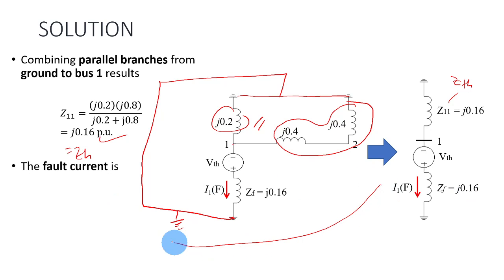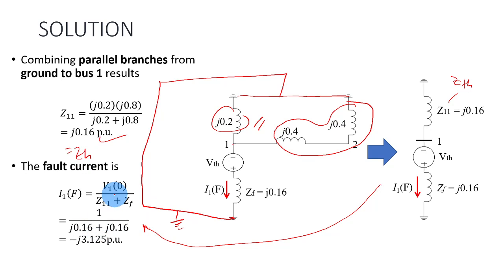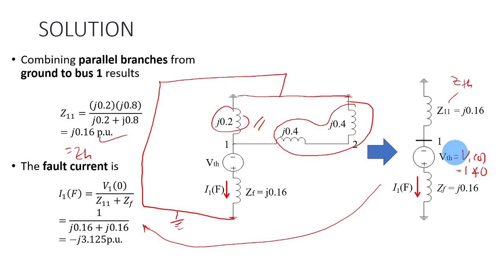From this reduced network, you can calculate the fault current using the formula. It's basically the fault voltage V1 before the fault, which is equal to 1 at an angle of 0. We assume all the voltages at all buses are 1 per unit. Unless you are given a certain value — if the value is not given, always assume it's 1 per unit. In normal condition, the system will try to fix the voltage at all locations at 1 per unit, meaning 100% rated value. For example, if a bus is rated at 132 kV, then 1 per unit equals 132 kV.